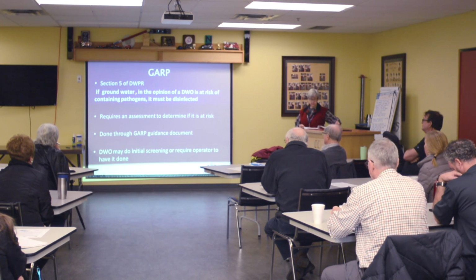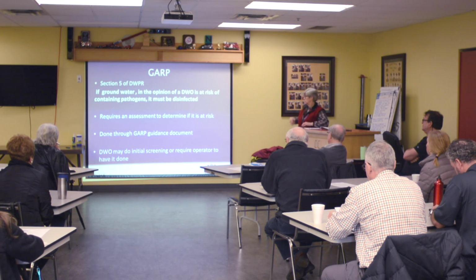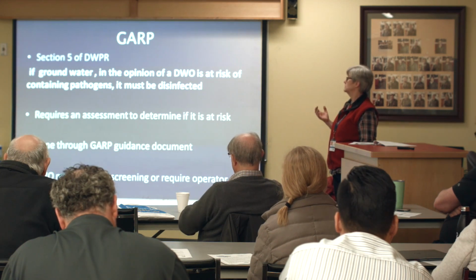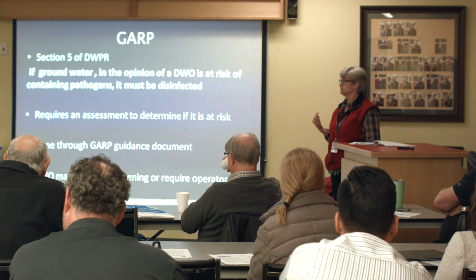Under Section 5 of the Drinking Water Protection Regulation, which is under the Drinking Water Protection Act, if groundwater, in the opinion of a drinking water officer, is at risk of containing pathogens, it must be disinfected. Drinking water officers are the environmental health officers that come around and look at your water systems and do the inspections, make recommendations, require you to make treatment, whatever is necessary.